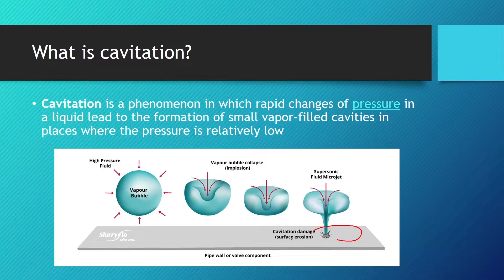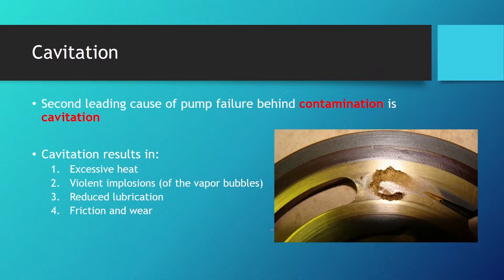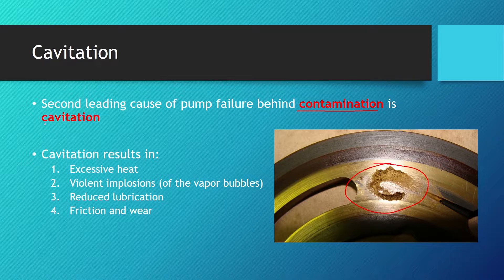Cavitation damage results in surface erosion. This does not happen with one bubble imploding — cavitation is something that happens over time. These microjets start to crack the surface, and within a year of using a pump that has cavitation bubbles you can see the damage on the components. We can see cavitation damage on an axial piston pump in this picture. The first reason for pump failure is contamination, but the second leading cause is actually cavitation.